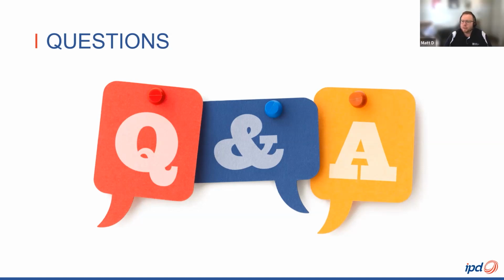Question here. New Zealand's been installing Type A's for longer than Australia. Is there a reason for this if the standard is shared? That's been the question asked many, many times for many, many years. You could say, and we hate to say it when New Zealand's ahead of Australia, but they are slightly more advanced in that. They recognised quite some years ago that electronics was coming into loads, and they made the decision that their minimum requirement was a Type A. In Australia, for whatever reason, it was decided that we would hold back. We've now made that choice, and we're aligning ourselves more with the New Zealand requirements within the standard.